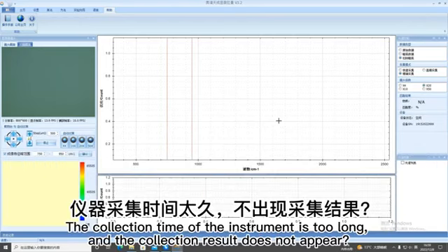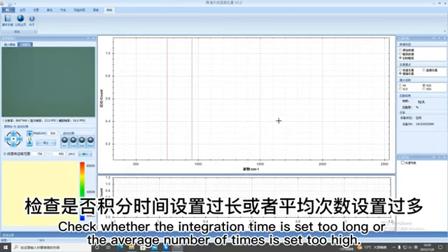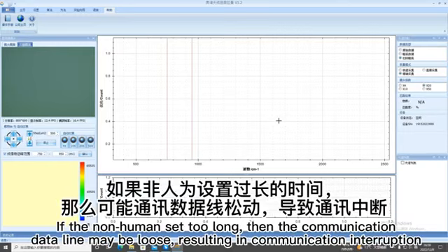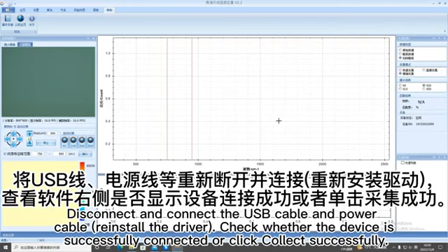The collection time of the instrument is too long, and the collection result does not appear. Check whether the integration time is set too long or the average number of times is set too high. If they are not set too long, then the communication data line may be loose, resulting in communication interruption. Disconnect and connect the USB cable and power cable. Reinstall the driver. Check whether the device is successfully connected and click collect again.